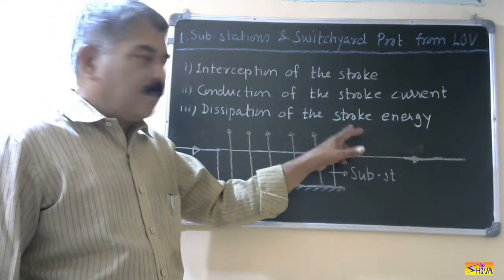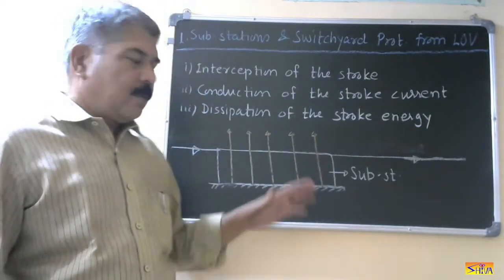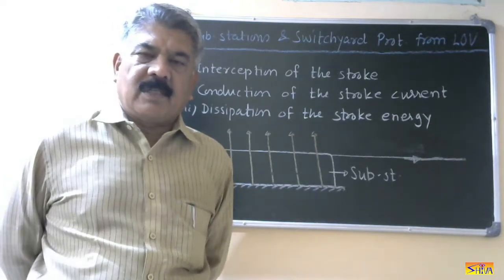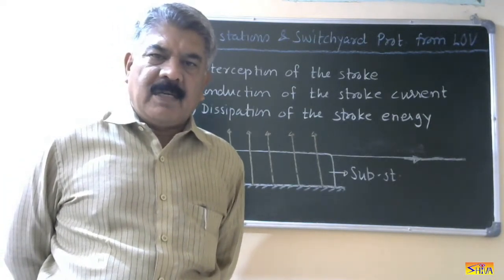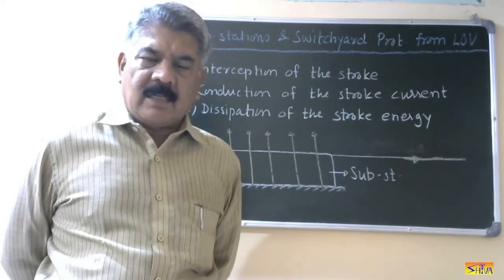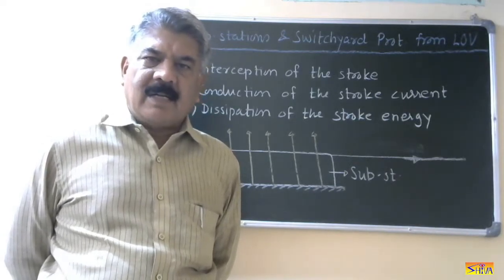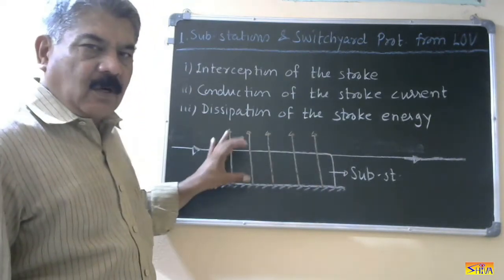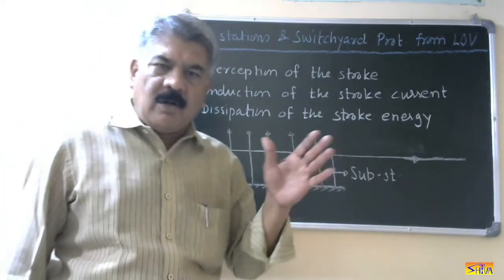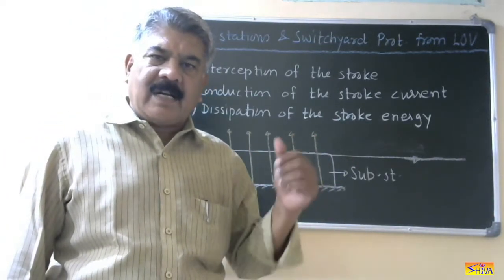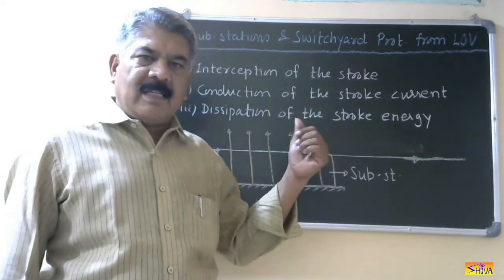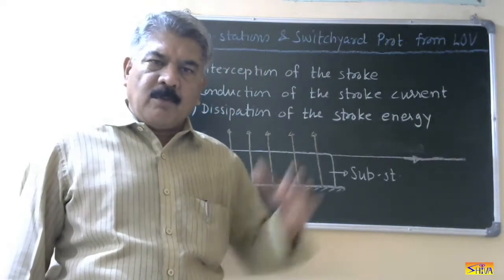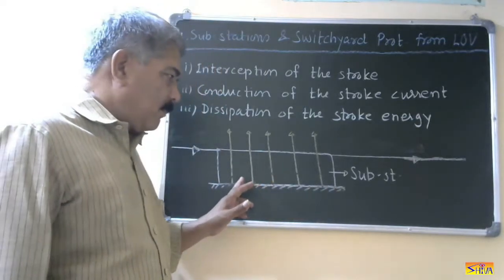The first step is interception of the stroke. In substations and switchyards there are various power system equipment such as transformers, CTs, PTs, lightning arresters, lightning surge absorbers, circuit breakers, relays, and isolators. Interception of the stroke means we want an object that will intercept or attract the lightning stroke, so that the lightning falls on that object rather than on the substation equipment. Since the stroke always hits the topmost object above the earth, we install metallic objects connected to ground.